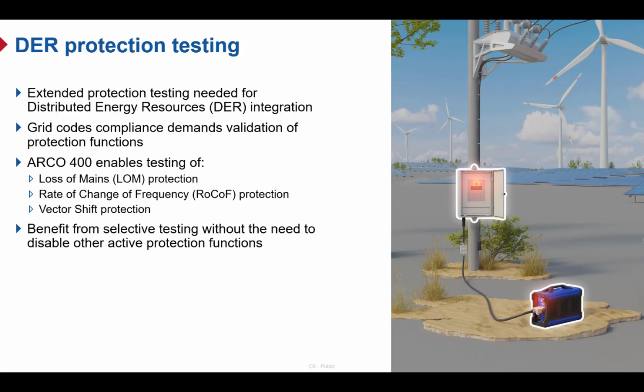Next, we will look at DER protection testing. With the increasing integration of distributed energy resources like solar and wind, protection requirements are becoming more advanced. Grid codes now require proper validation of these protection functions to ensure safe and stable operation. The ARCO 400 supports testing of the DER-related protection functions. This includes loss of mains protection, which detects when the grid is disconnected. It also includes rate of change of frequency, or RoCoF, which is used to detect rapid frequency changes. Another function is vector shift protection, which identifies sudden changes in phase angle. An important advantage is that you can test these functions selectively. This means you don't need to disable other protection functions during testing, which makes the process faster and more efficient.